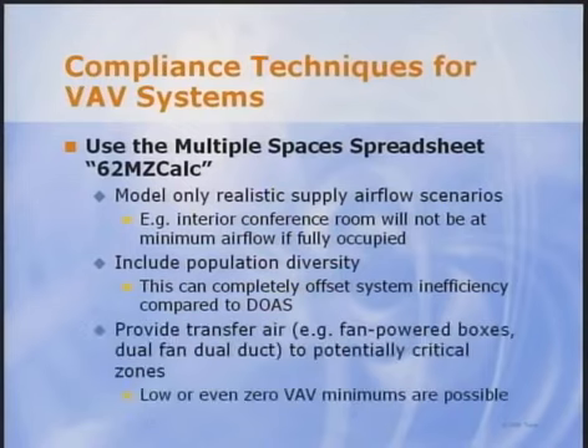Another tip, use transfer air on potentially critical zones. In other words, rather than raise the design or minimum airflow set points to spaces that are driving the system ventilation rate, use air transferred from other spaces or from the return system. Examples include fan-powered mixing boxes and dual fan, dual duct systems. Transfer air can reduce the system outdoor air rate by taking advantage of unused outside air from other spaces, and it also can improve zone ventilation effectiveness in the heating mode by reducing supply air temperature and maintaining diffuser throw. It also can reduce or even eliminate zone level reheat. I'll show you an example of that in a minute.